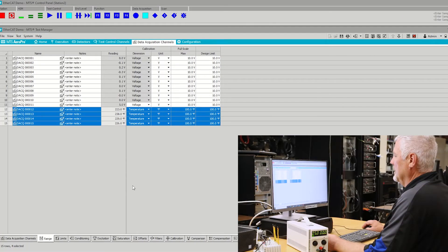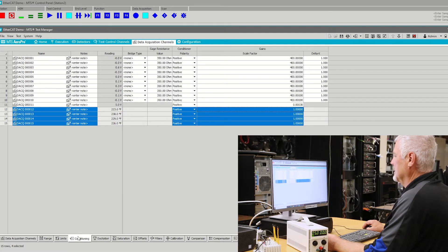To set up and calibrate EtherCAT channels, you must first go to the range tab, set the dimension, the unit, and the full scale. At this point you have two options for calibration. The first option is to set the scale factor on the conditioning tab.